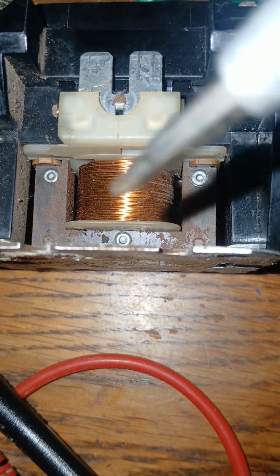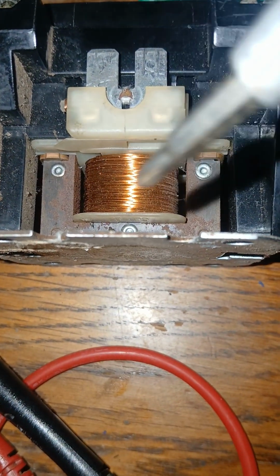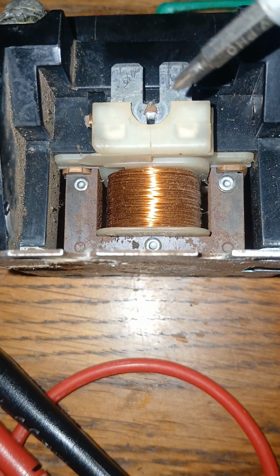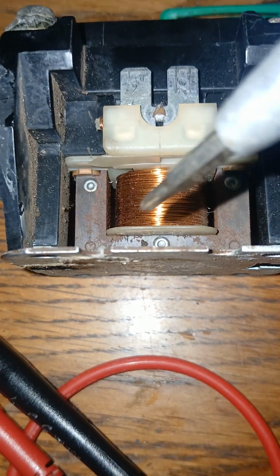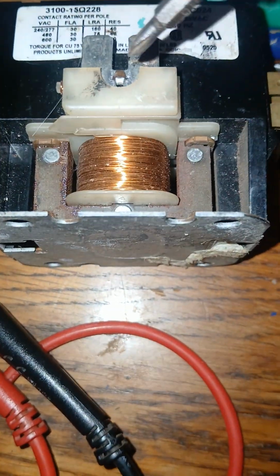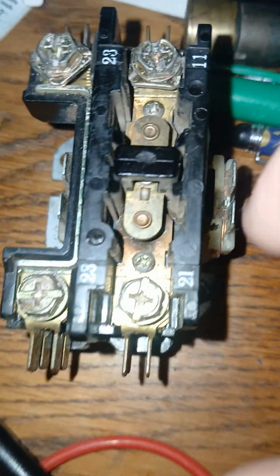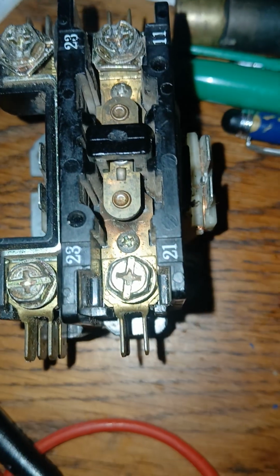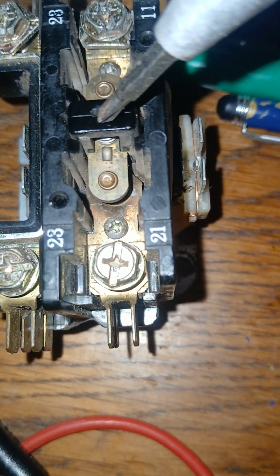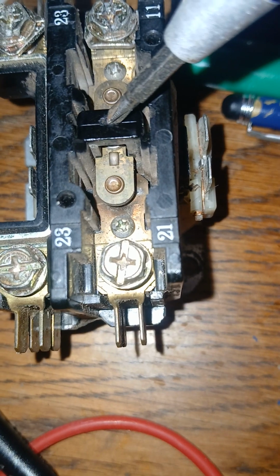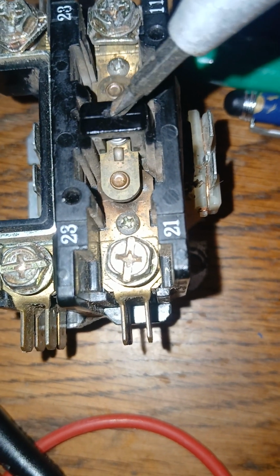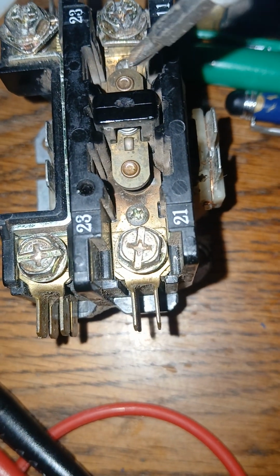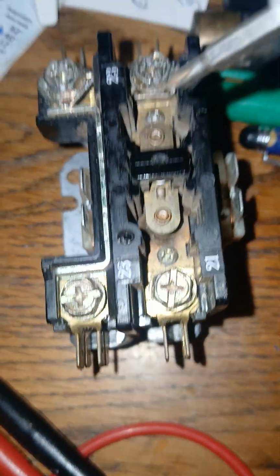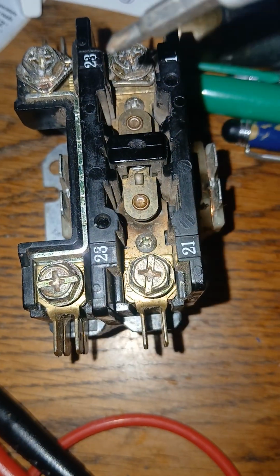Don't touch it with anything. You don't want to mess those, it looks like copper windings or something. But these are the low voltage side here, and then it energizes this coil. And then likewise on this side, this is the low voltage side. It energizes the coil. Once it energizes the coil, supposedly, if all things are working properly, we'll pull this in. Once it pulls that in, then this electricity, as you can see, this metal here touches this metal, so it allows this electricity and this electricity to go from each side.